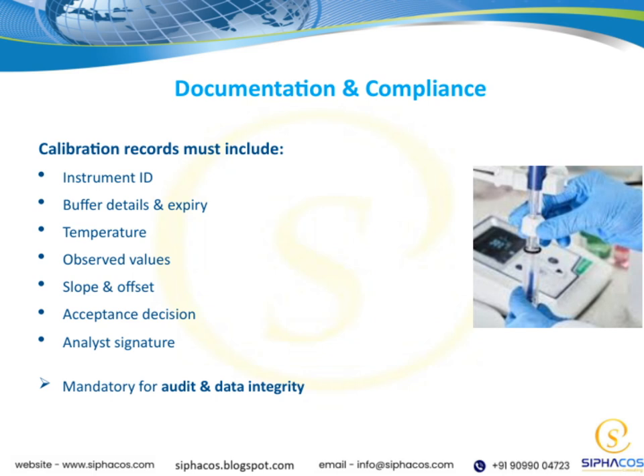Observed values must be documented carefully. That's the actual reading obtained during calibration. We also need to note the slope and offset, which are critical for understanding the instrument's performance. The acceptance decision is the final step, whether the instrument passes or requires adjustment, and this should be clearly recorded. Lastly, the analyst's signature acts as a verification that all these details are accurate and complete.